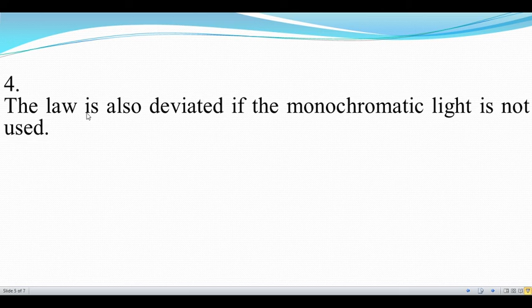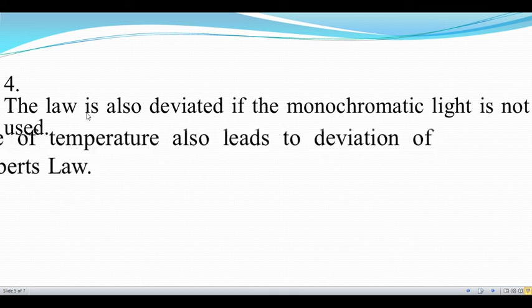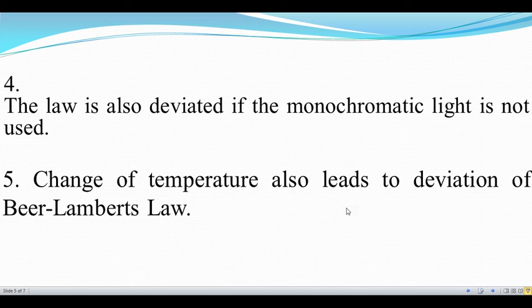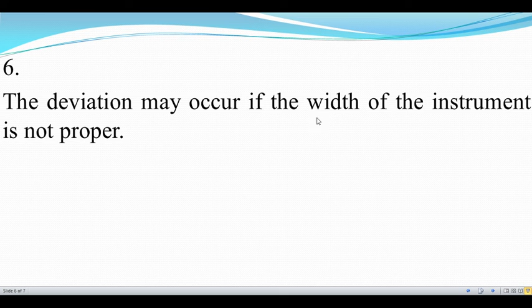The fourth limitation is the law is also deviated if the monochromatic light is not used. And fifth one is change of temperature also leads to deviation of Beer-Lambert law. Sixth, the deviation may occur if the width of the instrument slit is not proper. Seventh, the deviation also occurs in the instrument where filters are used, because with filters we do not get monochromatic lights.